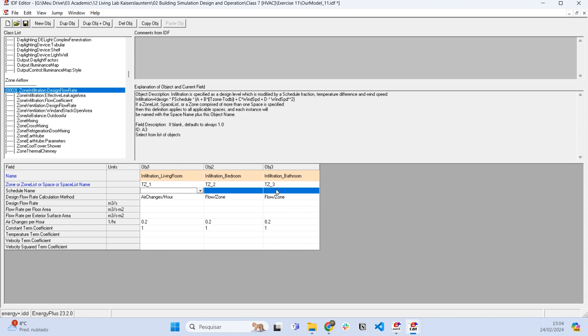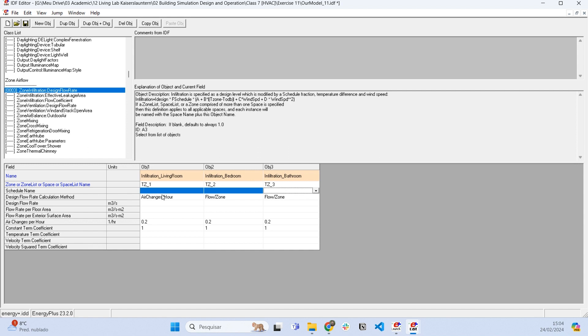When the air conditioning is working, it blows air inside the building and because of the difference of pressure, there is no infiltration. We usually model the schedule of the infiltration as the opposite of the schedule of the air conditioning.